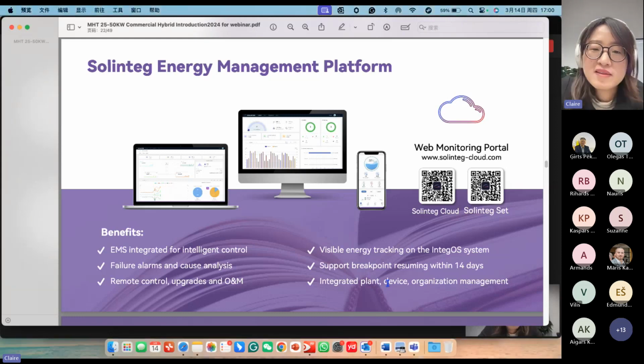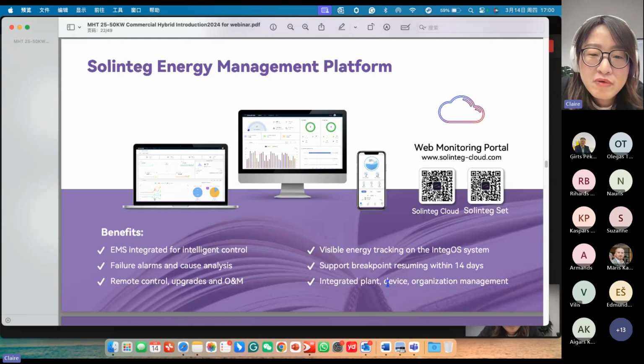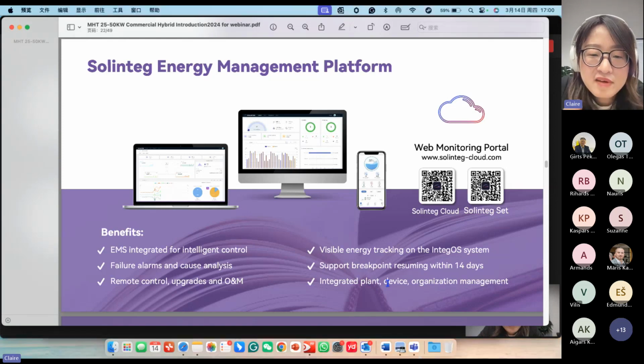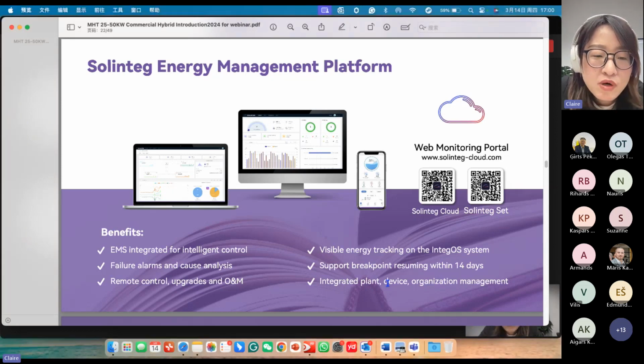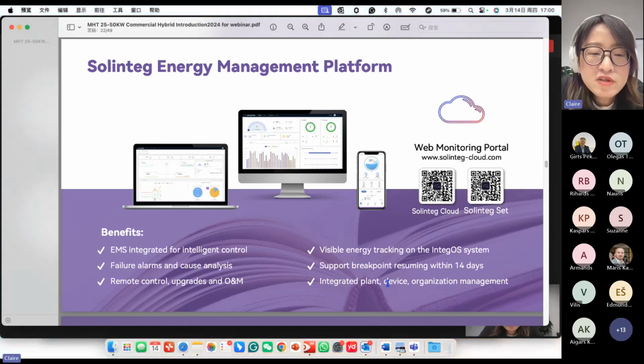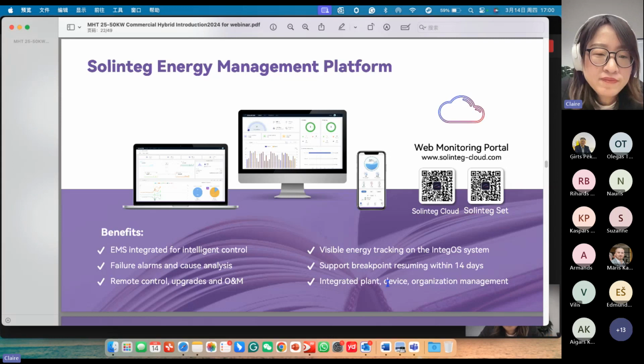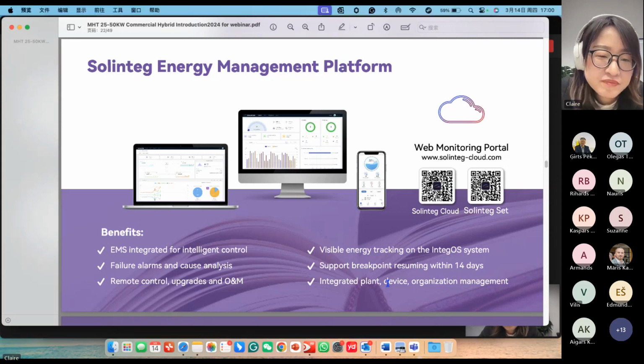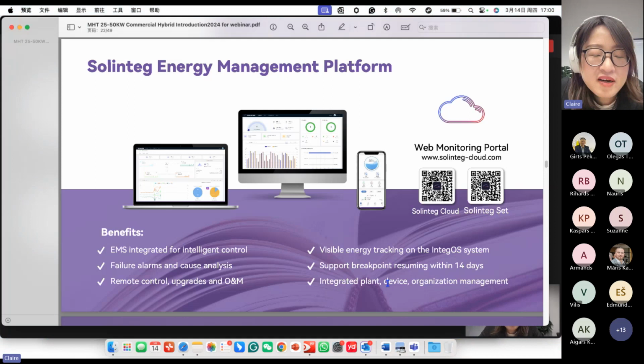We can schedule the upgrading of the new version. Sometimes the customer may not want to upgrade firmware during working time, because if the inverter is generating power while doing the firmware upgrading, after upgrading the inverter will restart, and this will take about 5 to 10 minutes. In these 5 to 10 minutes, the customer doesn't have any power generation, so they can schedule the upgrade at night. So this won't influence their power generation.